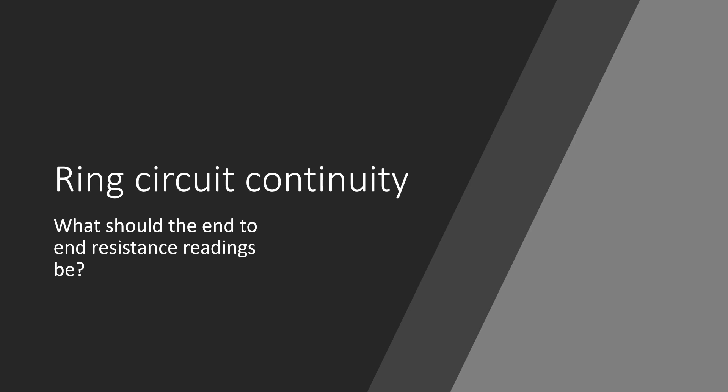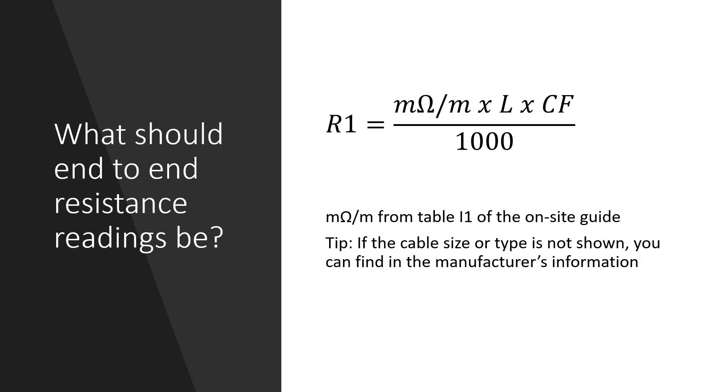To find out what we should expect the readings to be we can find the answer in table I1 of the on-site guide. Table I1 provides values of milliohms per meter for various cable sizes which we can use to work out what to expect the readings to be by multiplying the value by the length and a correction factor and then dividing by 1000.